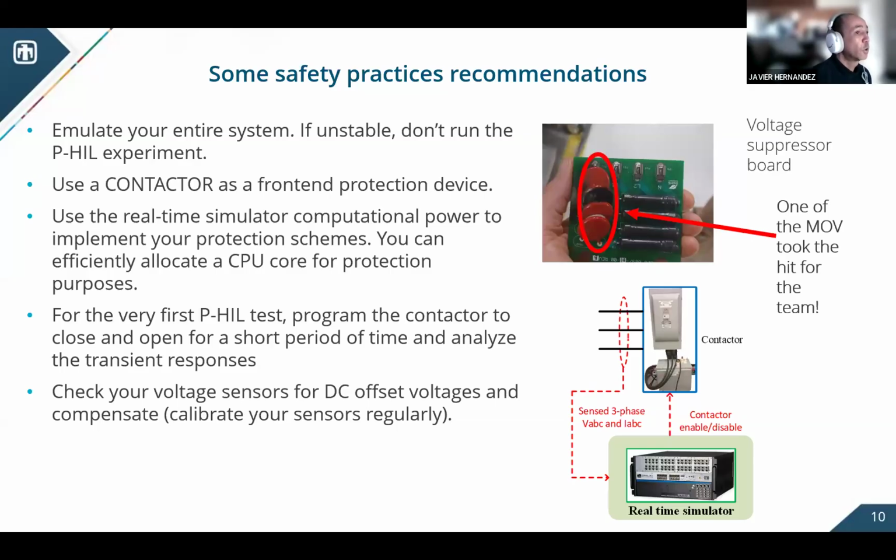And if this is going to be your very first P-HIL test with that particular unit, program the contactor to just operate for a short period of time, and then analyze the transient response. I will show some of the testing that we do here at Sandia, and our first initial test is for synchronization, and we try to do it for 1 second.